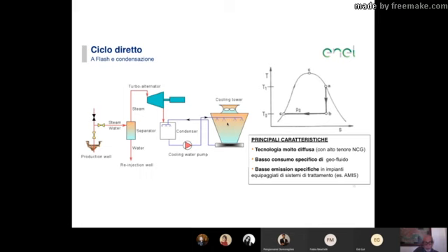So during the day, you can lose 75–80% of your geothermal fluid by evaporation into the atmosphere. So your emissions from the geothermal power plant are going to be very much, and very little is reinjected back into the geothermal system. In winter, when the air is colder, then it is not so much, and perhaps only half of the fluid is lost to the atmosphere.